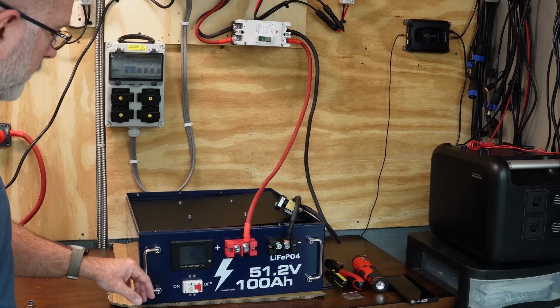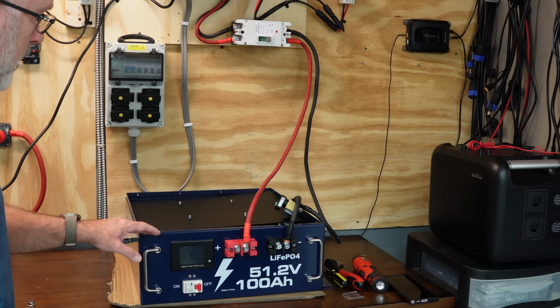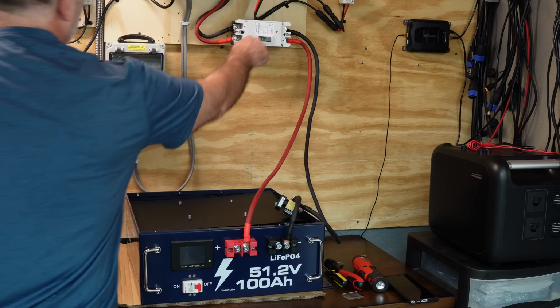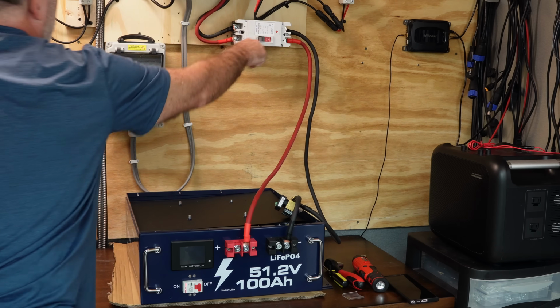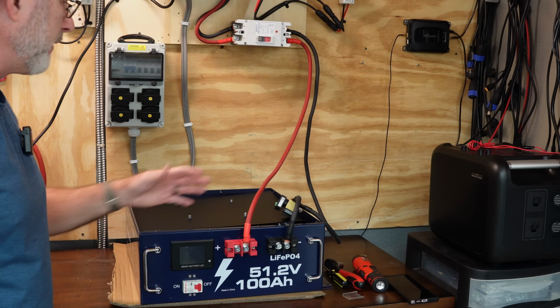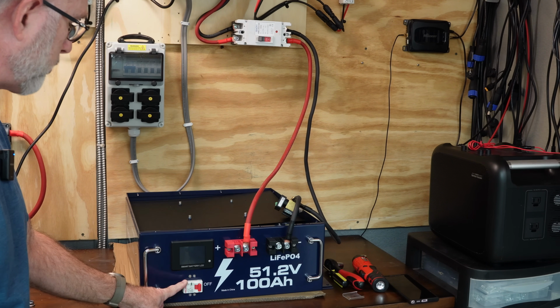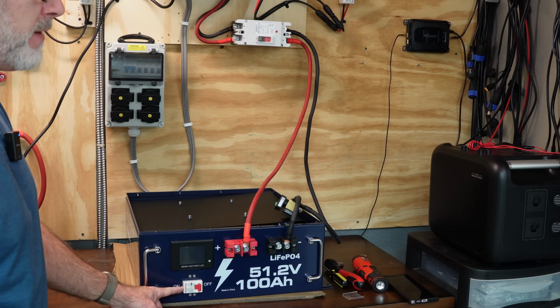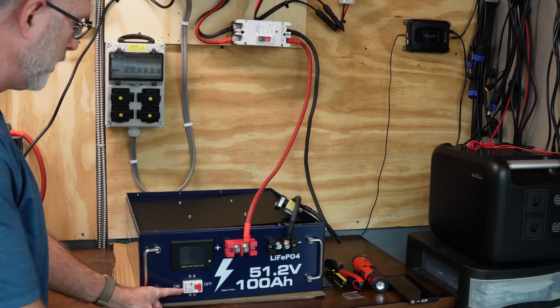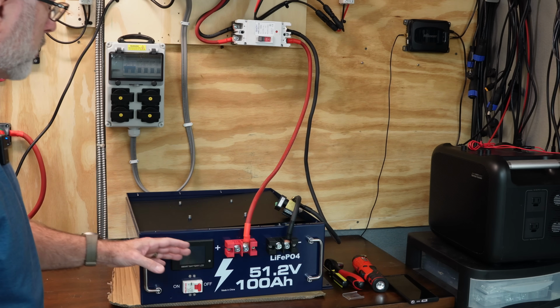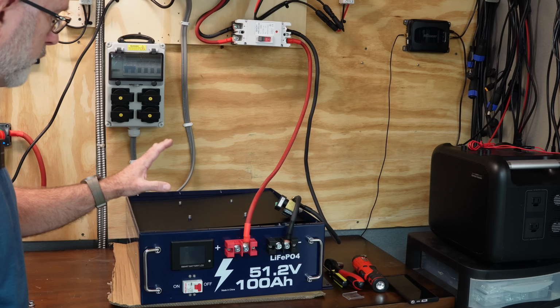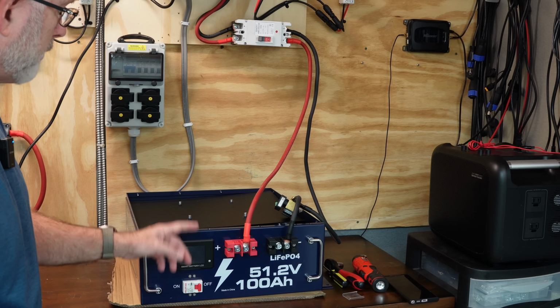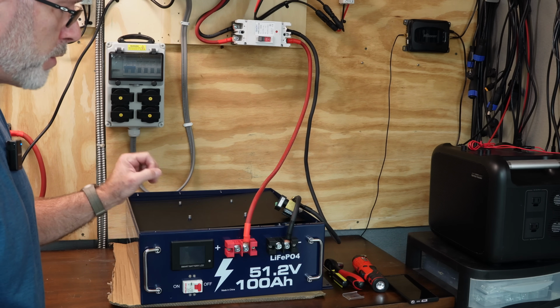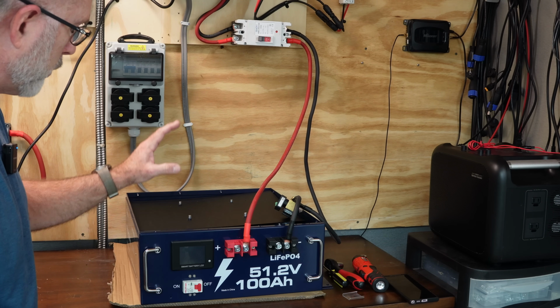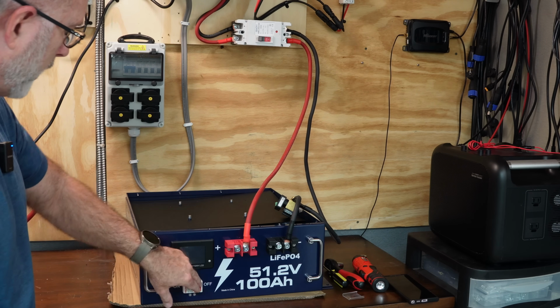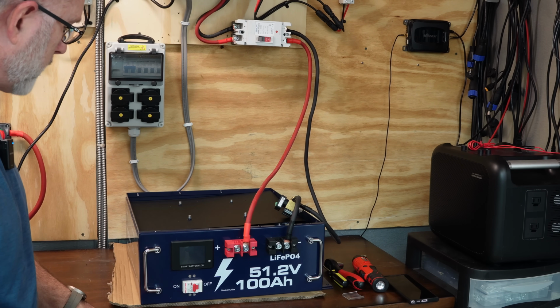And one thing I wanted to point out too is that the proper way to start one of these up, you want to turn on the breaker first to your AC inverter so that you have a live connection to the AC inverter. And then you turn on this breaker here on the bottom. This will activate the pre-charge resistor circuit that's in here to make sure that we don't flood a bunch of current to charge the capacitors on the inverter very quickly. So it'll trickle charge the inverter capacitors safely. And to do that, we turn this breaker on here.